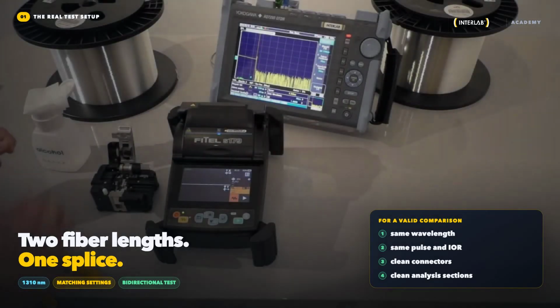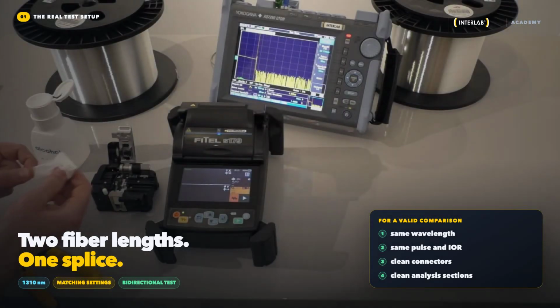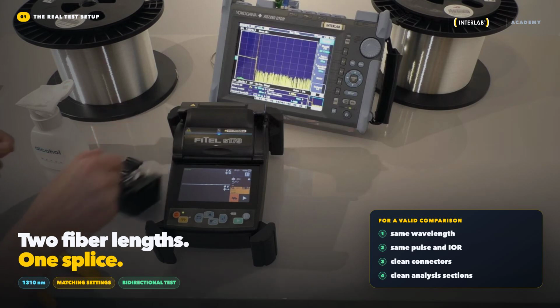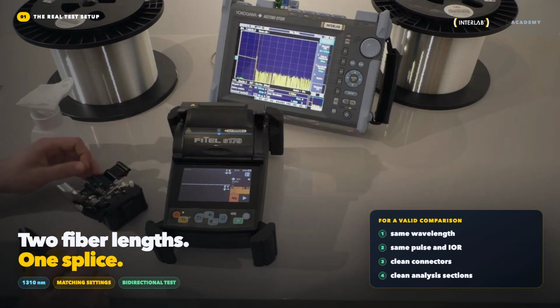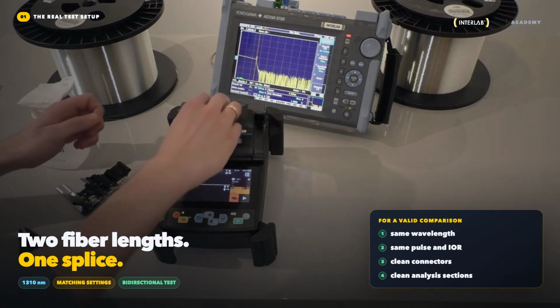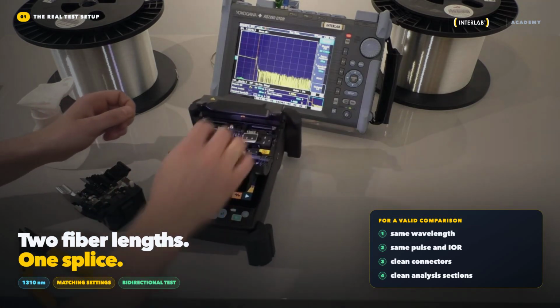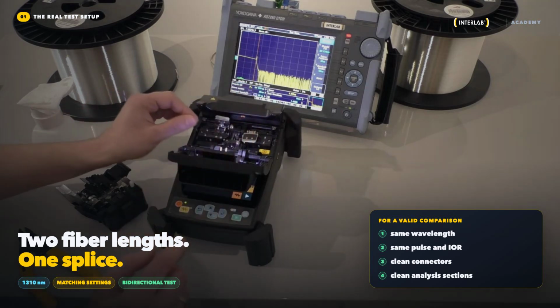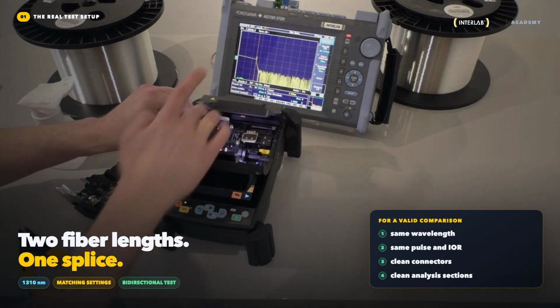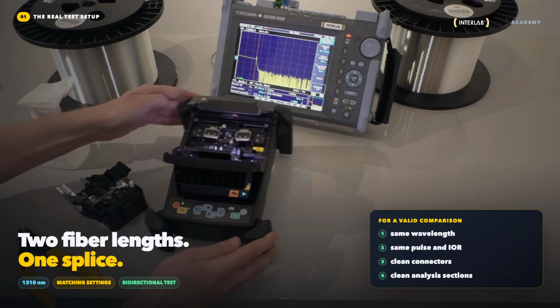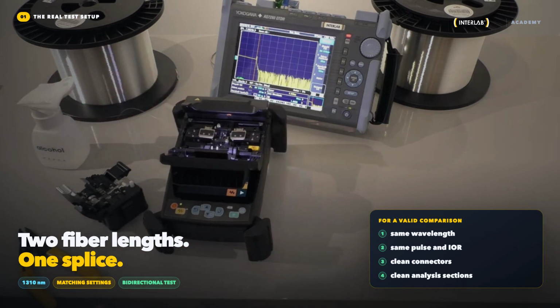On the INTERLAB test bench, we have two lengths of fiber joined by a single splice and a Yokogawa OTDR. First, we measure the link from side A. We save the trace, swap the fiber ends, and run the second measurement from side B. The test conditions stay the same: a wavelength of 1310 nanometers, the same pulse width, refractive index, and averaging time. These are not two different splices or two different test setups. The only thing we change is the direction from which the instrument sees the same event.